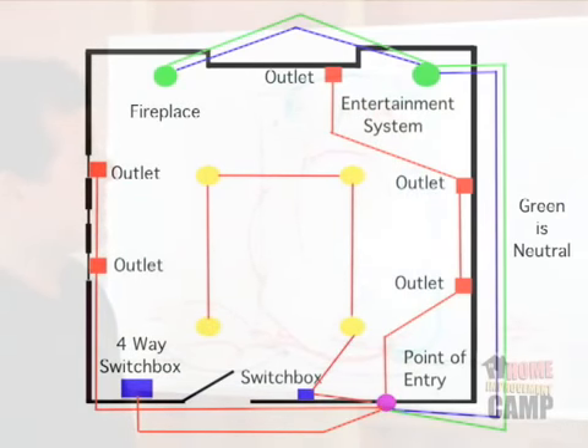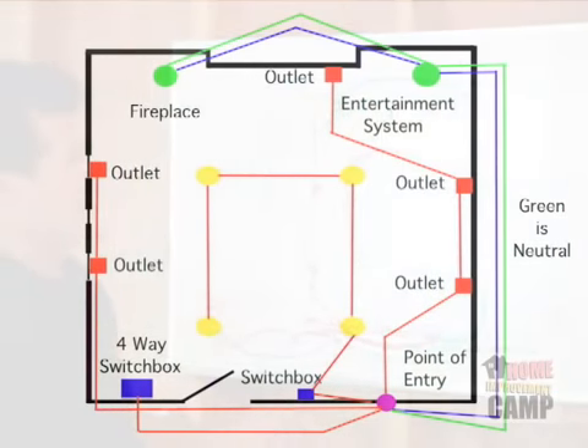Adding a four-way switch is pretty simple. Basically what you're going to do is break your traveler legs and insert a four-way switch. If for some reason you needed to add another four-way switch, that's pretty simple too—you're just going to add another one.